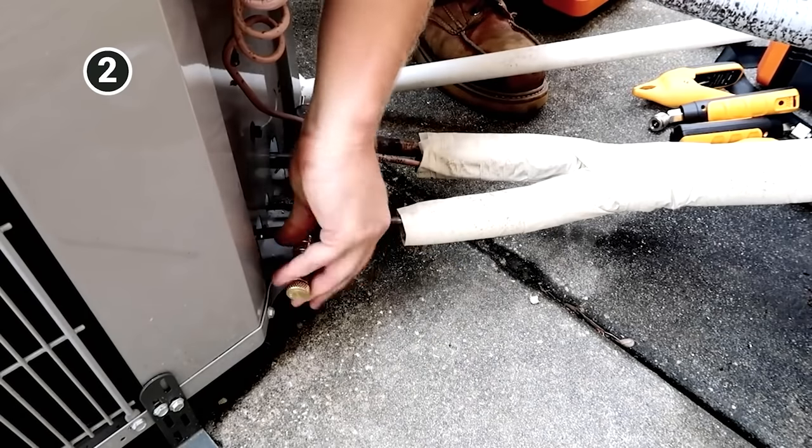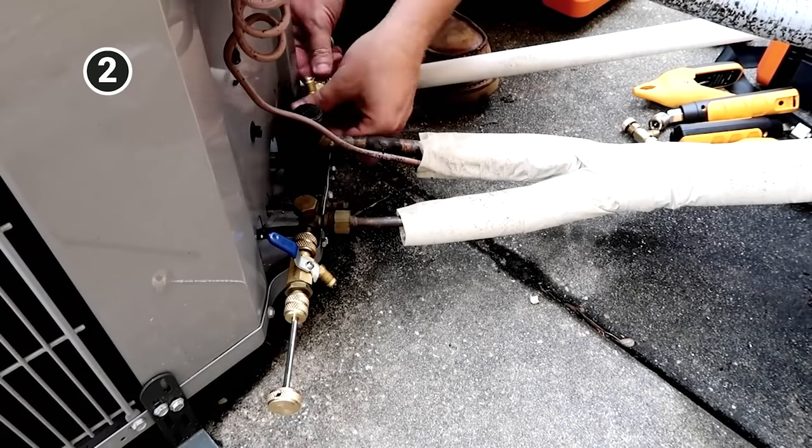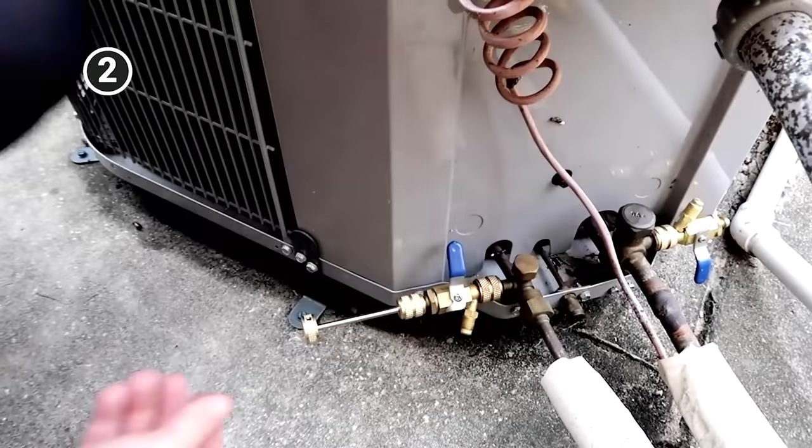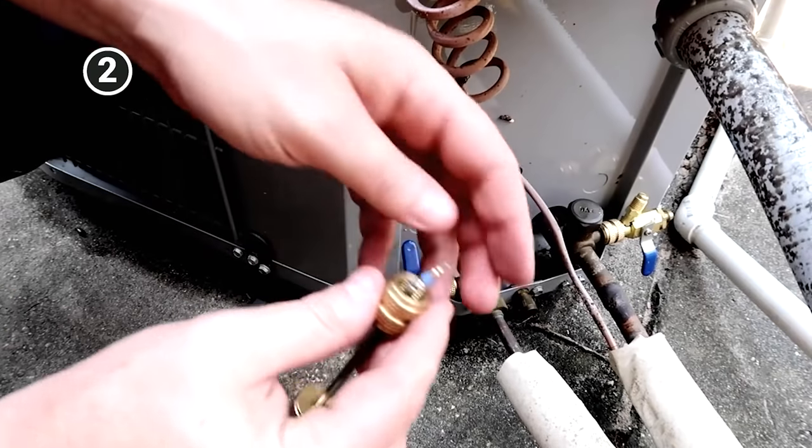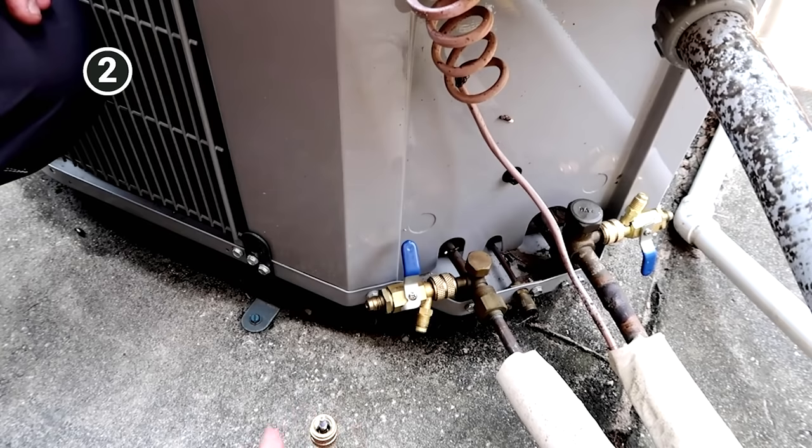If you want to go ahead at that point and pull your cores out, put your core remover tools on. That's going to be a really good practice just to help prevent anything from getting in that system, especially if you're going to be cutting that system out or maybe even unsweating certain parts of it, which sometimes that's just a practical thing to do. You want to have a little bit of nitrogen flowing at that point.